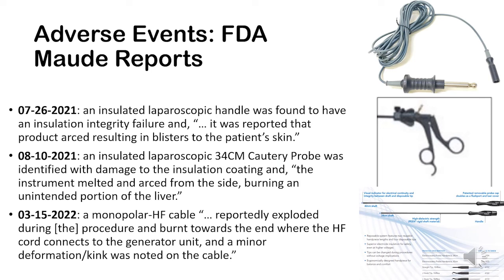In the FDA MAUDE reporting system, there were adverse events. In July of 2021, an insulated laparoscopic handle was found to have an insulation integrity failure, and it was reported that the product arced, resulting in blisters to the patient's skin. In August of the same year, an insulated laparoscopic cautery probe was identified with damage to the insulation coating, and the instrument melted and arced from the side, burning an unintended portion of the liver. In March of 2022, a monopolar cable reportedly exploded during the procedure, burnt towards the end where the cord connects to the generator unit, and a minor deformation or kink was noted on the cable.